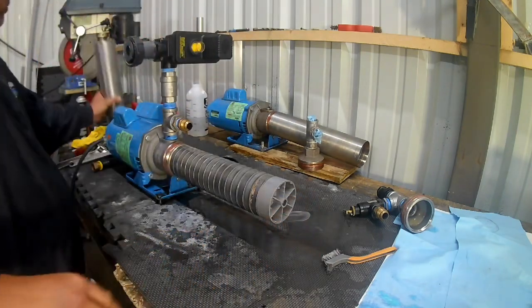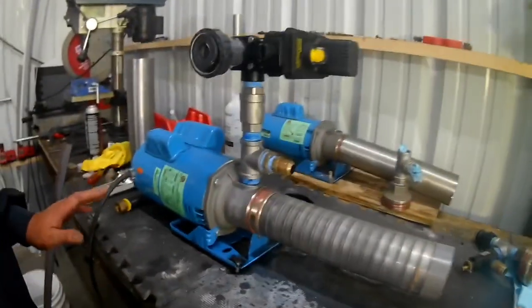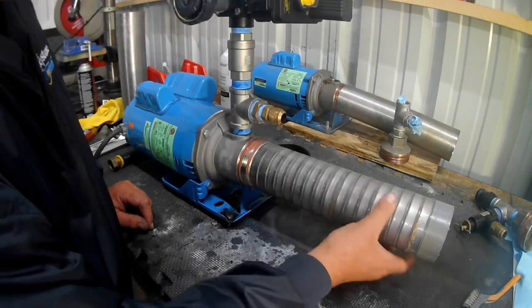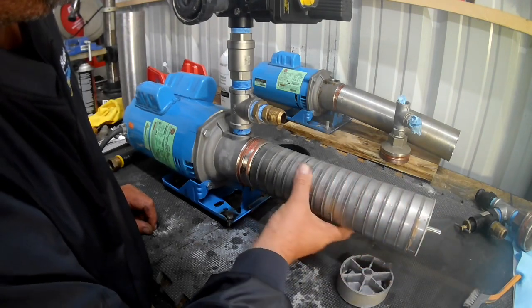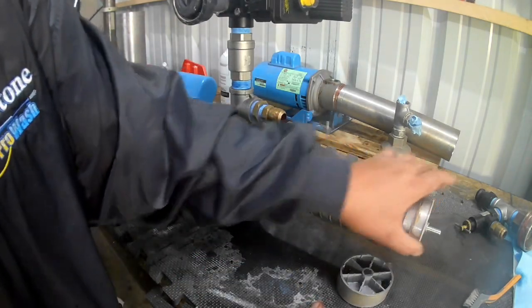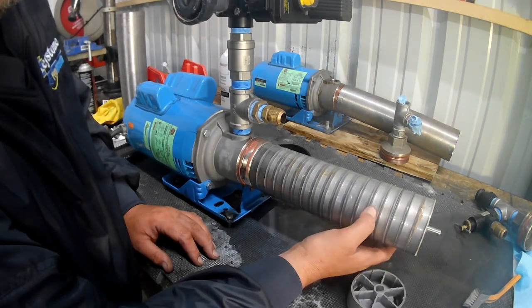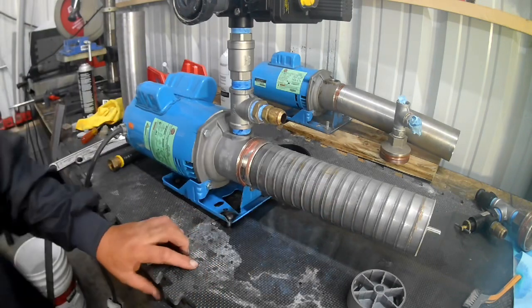This is what it looks like — now closer. See how these all spin freely? There's a little bit of slack in here — that's probably a little too much slack, not enough spacers on the end. But it's not necessarily a bad thing. When you start building up scale on this, it starts to actually get tighter. Now I'm going to show you what happened to the other one.